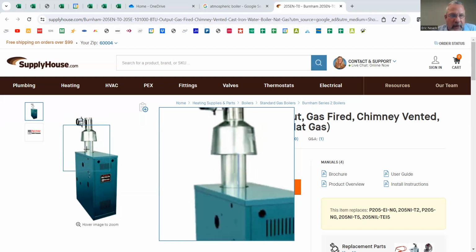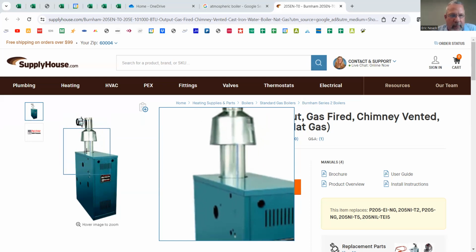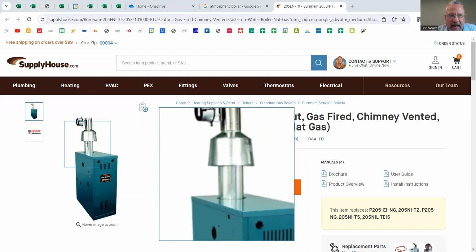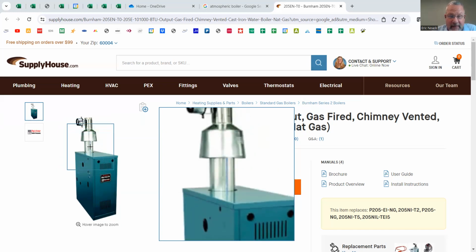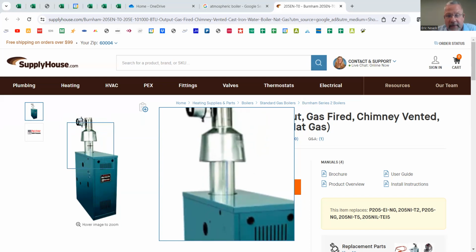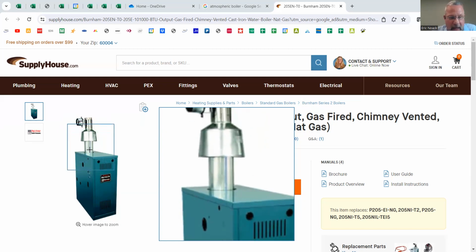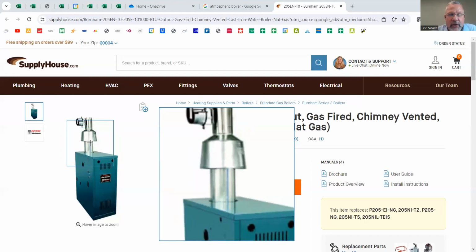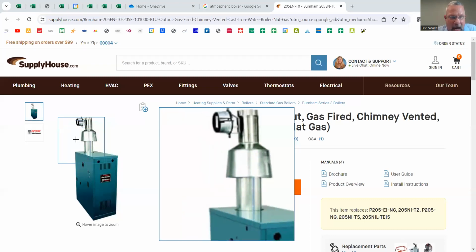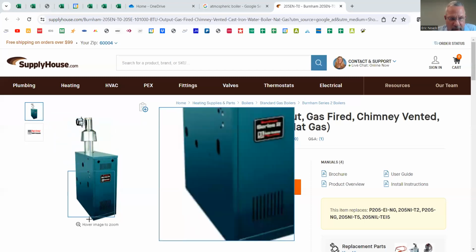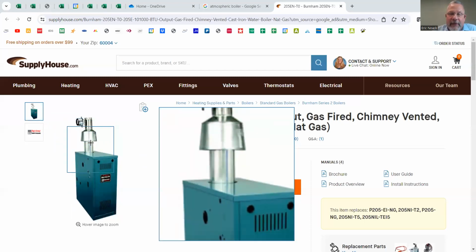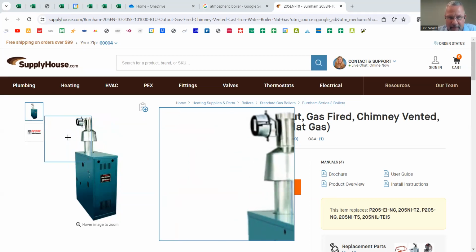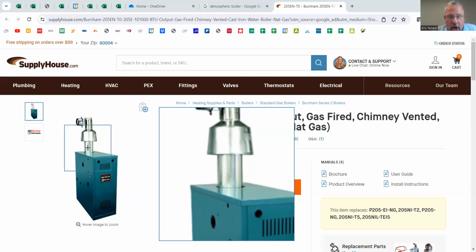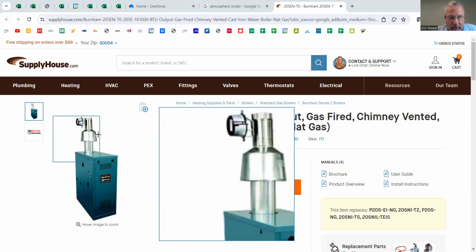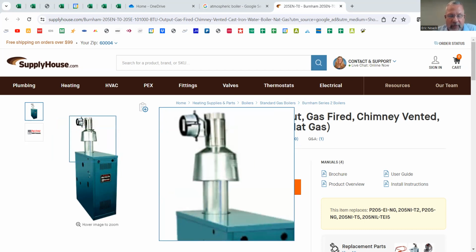The point that I wanted to make here, though, is this distance between the top of the boiler where this pipe connects and the bottom of this atmospheric damper bell, that's fixed. It'll say right on the pipe, do not cut, can't trim it, it must remain. You can't change that. So the problem occurs if that outlet or connection place is too low and this new boiler is taller than the old one. Now they're going to have a problem getting that pipe to connect. So it's really important to know that margin. What is the distance from the floor to that flue connection that we need to hook up to? And is the new boiler going to be compatible with that or not?